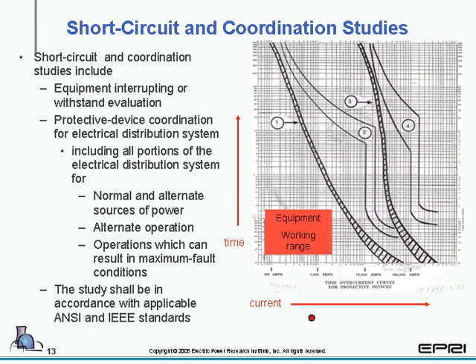If you look, as current increases, you will see that the breaker will come offline as time decreases. If this breaker is seeing roughly 50 amps, if you follow the chart up, it will never trip. It's working in its working range. But if we go over to 1,000 amps and we follow it up, it'll cross the line at some point in time. And if we follow that over, it's roughly 8 to 9 seconds before the breaker will trip. If whatever protection that is fails to operate, it will continue up and stay in service for roughly 100 seconds before it trips offline. But most likely it would take not only that equipment, but other equipment with it.